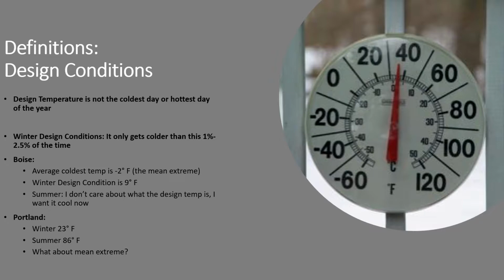Design temperature is not the coldest day of the year or the hottest day of the year. Usually the coldest day of the year happens at 2 or 3 in the morning. Chances are the house has enough thermal mass that it's already heated up and can ride through those few cold hours. If we sized equipment for the hottest or coldest day of the year, we would probably have 2 systems in every house, and everything would cycle and cause lots of comfort complaints. Winter design condition means it only gets colder than that 1 or 2.5% of the time, depending on what number you tend to use. In Boise, the average coldest temperature is -2. This is also called the mean extreme. However, the winter design condition is 9.